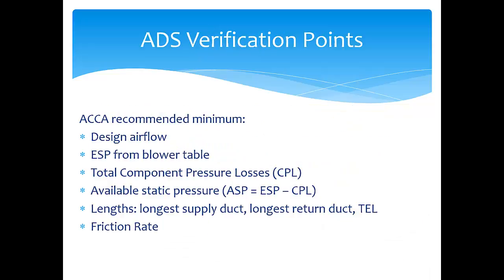That brings us to the ACCA recommended verification points for duct sizing. We've come up with six essential points that are pretty easy to verify: first, the design airflow for the blower; second, the associated external static pressure at that airflow — both easy to verify from the blower table; third, the component pressure losses (sum of losses from the coil, filters, grills, registers, etc.); fourth, an arithmetic check that available static pressure = ESP minus CPL; fifth, verify the total effective length used in the friction rate equation for the longest path; and sixth, confirm the friction rate falls within the wedge and was calculated correctly.